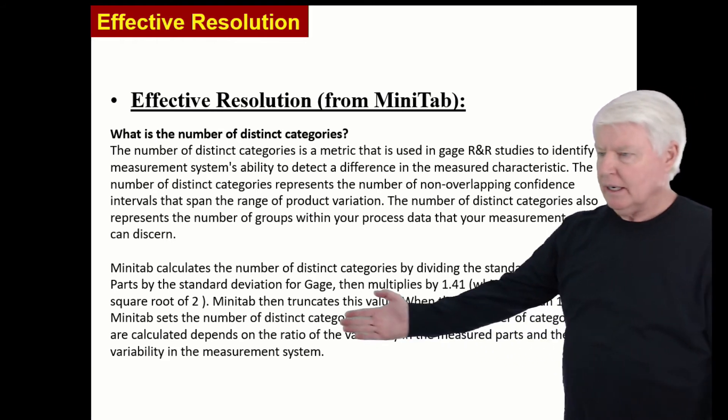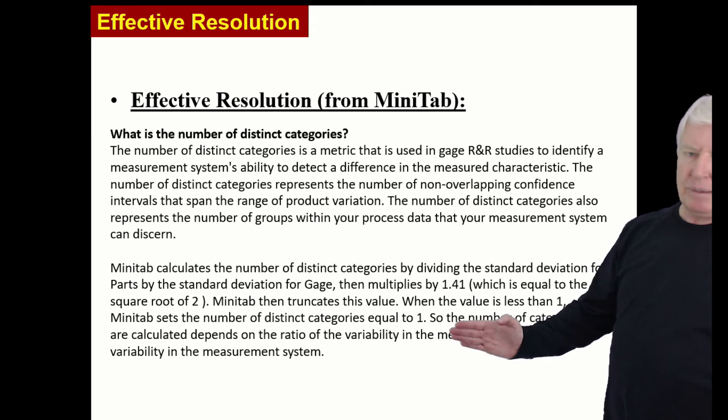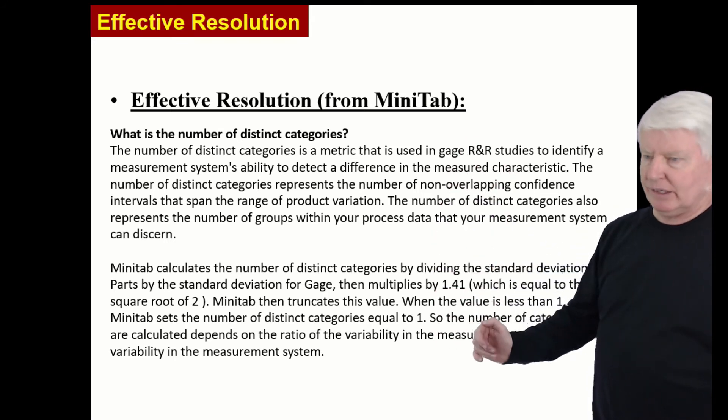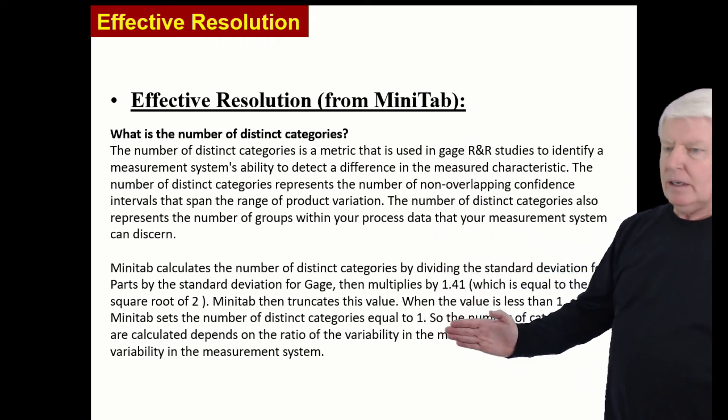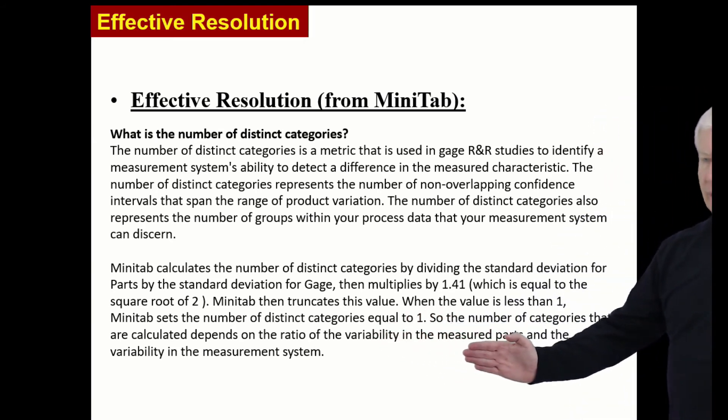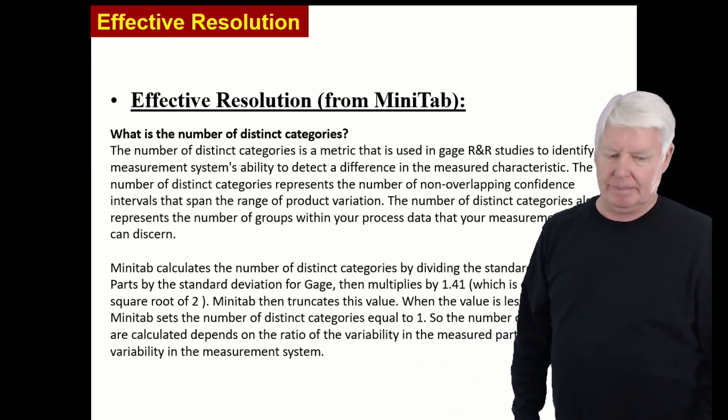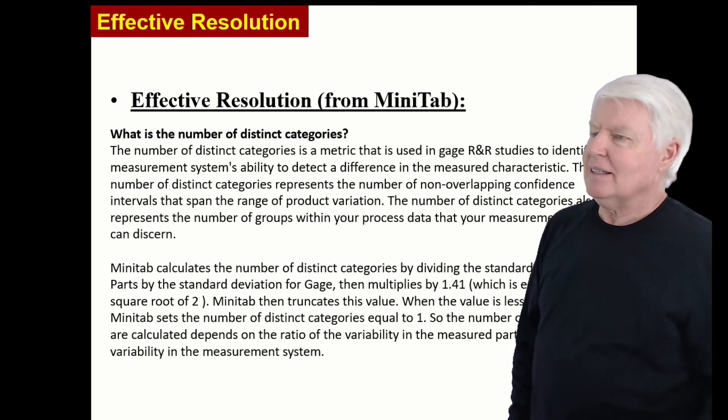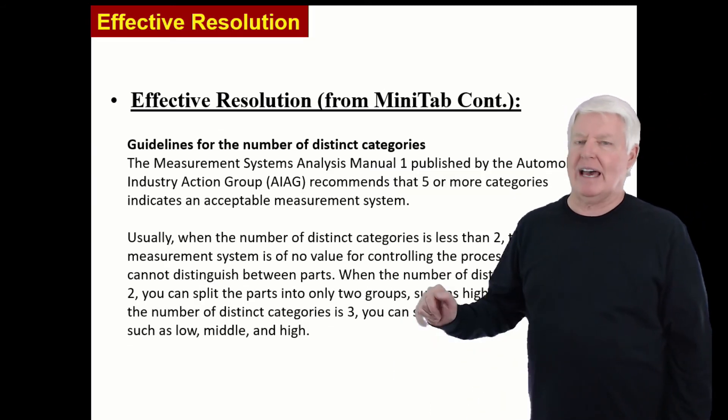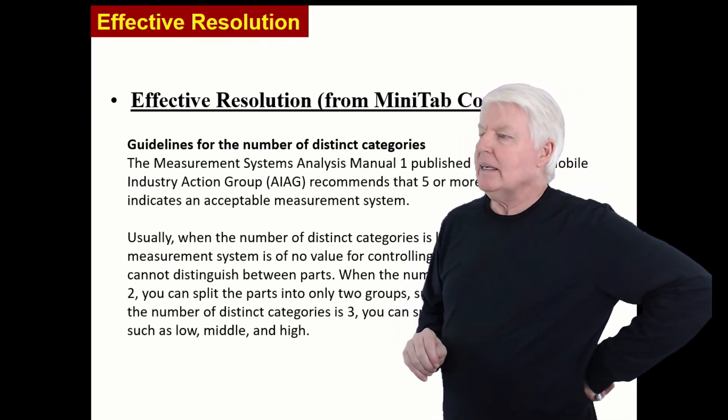Minitab then truncates this value. When the value is less than 1, Minitab sets the number of distinct categories equal to 1. So that'd be one what? One column on your histogram, as I mentioned earlier. So the number of categories that are calculated depends on the ratio of the variability in the measured part, sigma of the parts, and the variability in the measurement system. So there you go. And you may need to listen to that a couple times. I know I've had to do that in many of these vocabulary studies.